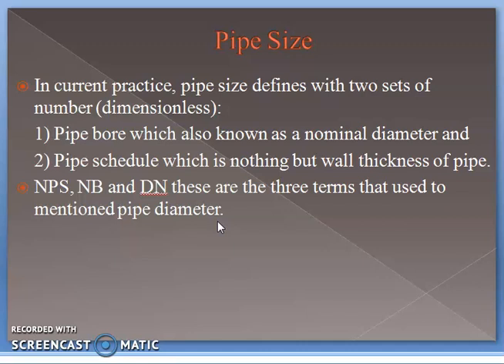In current practice, pipe size is defined with two sets of dimensionless numbers. The first is pipe bore, also known as nominal diameter, and the second is pipe schedule, which defines the wall thickness of the pipe. NPS (Nominal Pipe Size), NB (Nominal Bore), and DN (Diameter Nominal) are the three terms used to refer to pipe diameter.